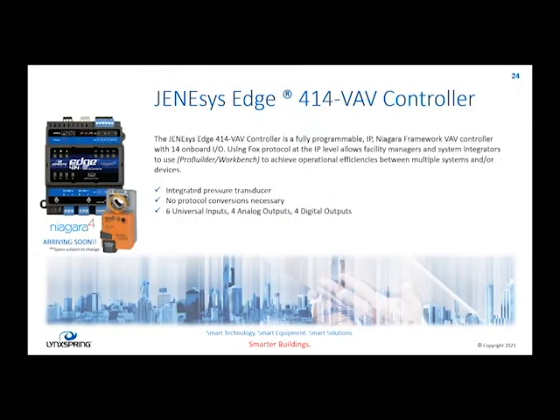So just real quickly, we are releasing version 2.0 of the JENEsys Edge. If you're unfamiliar with the VAV products that we currently have, it is a 14 points of I/O onboard, fully Niagara programmable controller. So with your normal Workbench, you can go in and modify, change the programming, get into everything that you have. It's got an integrated pressure transducer. It's got the 4 analog outputs, 4 digital outputs, and 6 universal inputs.